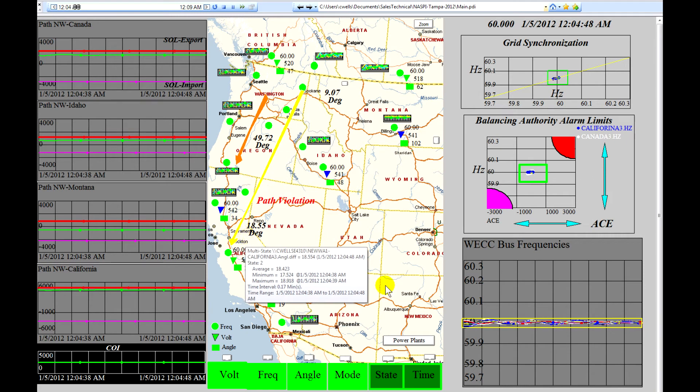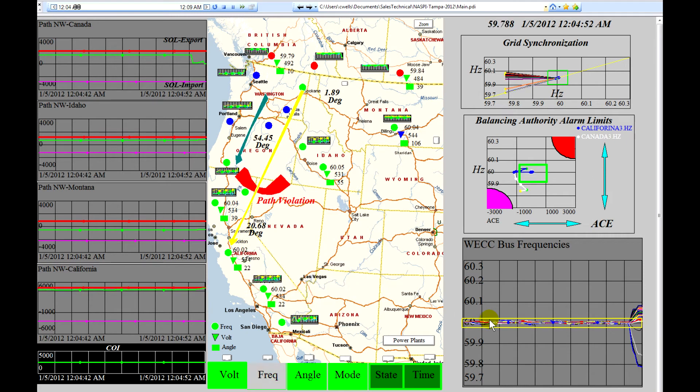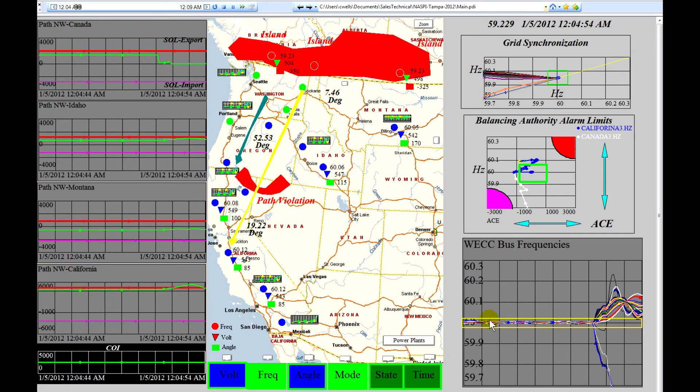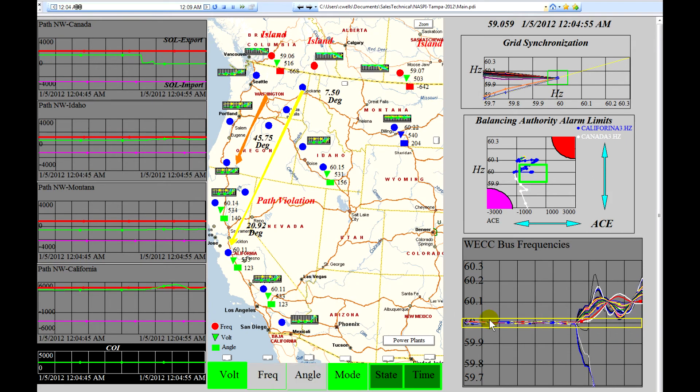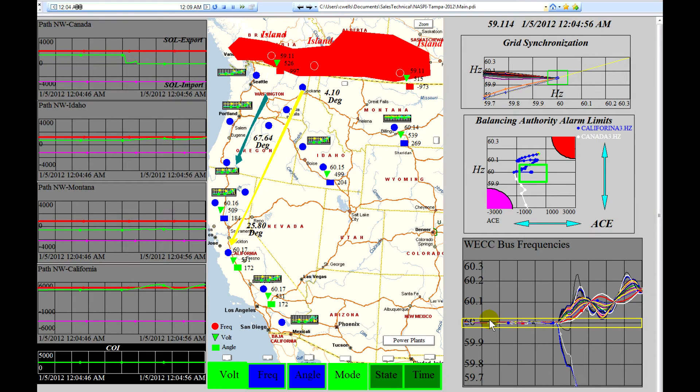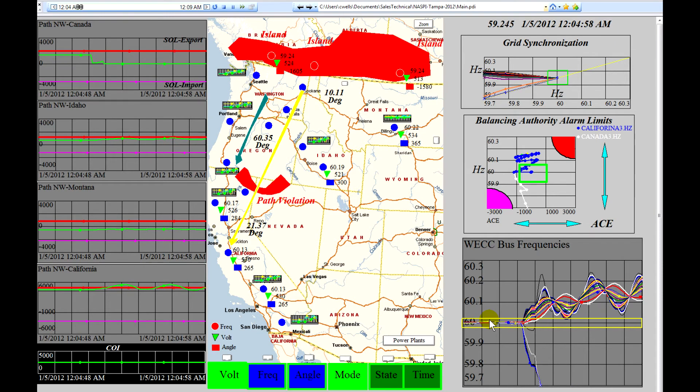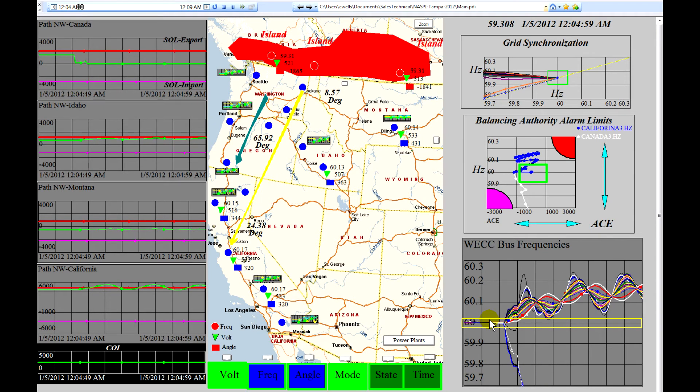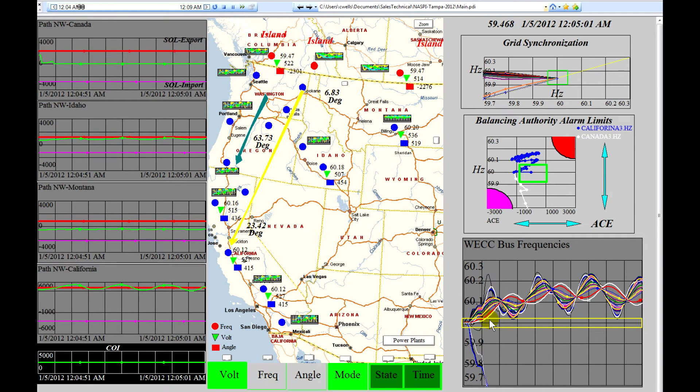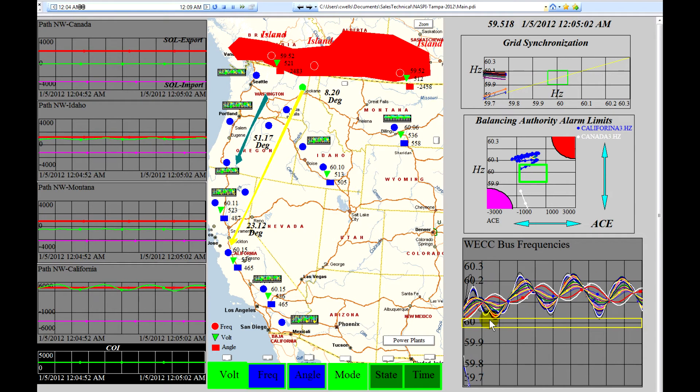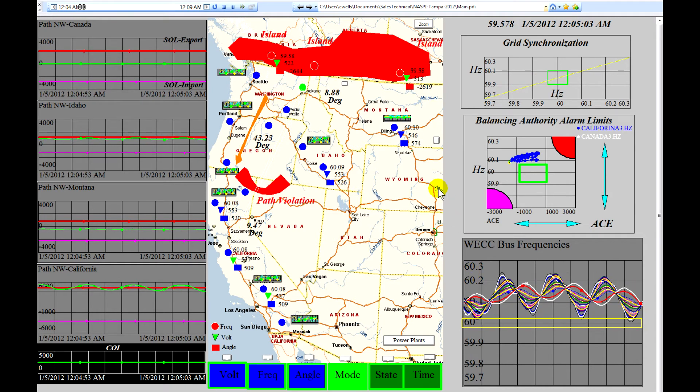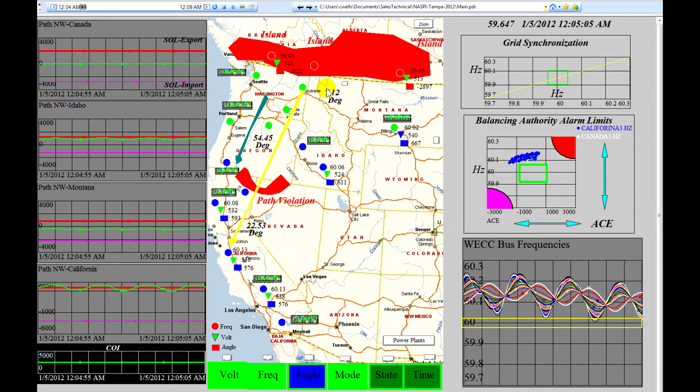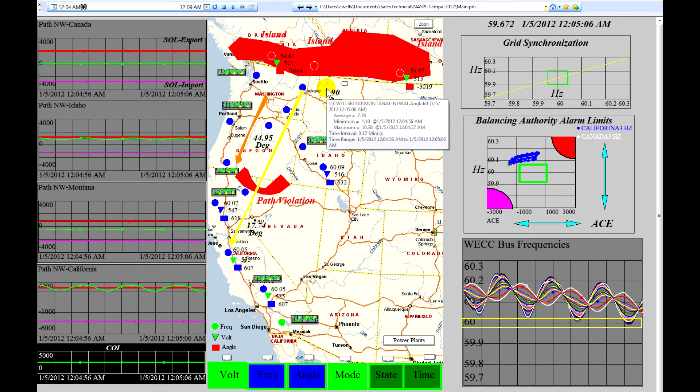Now, the frequencies have now stabilized after the first event. But now it appears that there's been a major separation between Canada and United States. This is shown by the automatic island detection system that recognizes that there has been a separation.